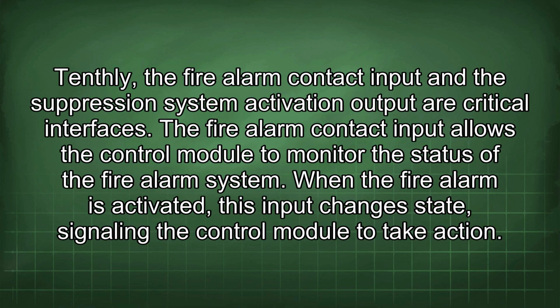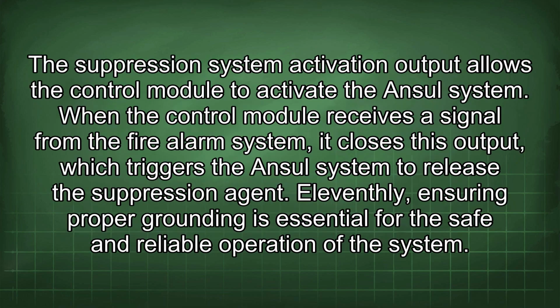Tenthly, the fire alarm contact input and the suppression system activation output are critical interfaces. The fire alarm contact input allows the control module to monitor the status of the fire alarm system. When the fire alarm is activated, this input changes state, signaling the control module to take action. The suppression system activation output allows the control module to activate the Ansul system. When the control module receives a signal from the fire alarm system, it closes this output, which triggers the Ansul system to release the suppression agent.